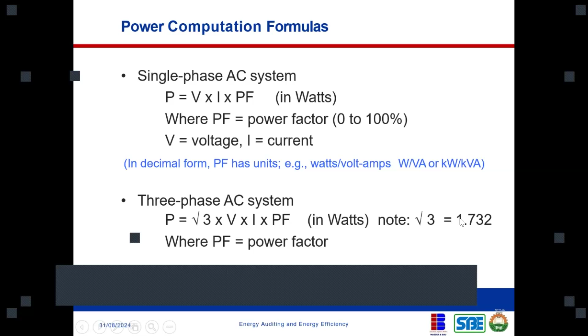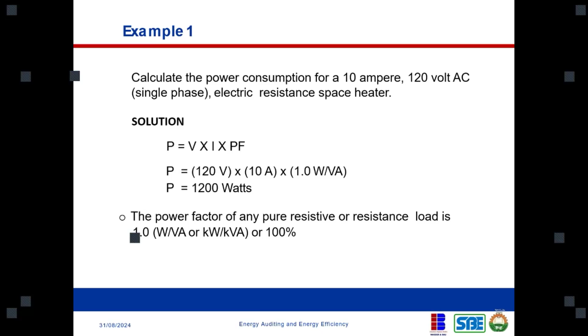So this is an example, a straightforward one. The formula is straightforward, you just need to extract your values and input them into the formula, then run a simple calculation. This asks: calculate the power consumption of a 10 ampere, 120 volt AC single phase electric resistance space heater. You'll be given your current, your voltage, and your power factor. For a resistive load, the power factor is just 100 or 1. So it's a straightforward calculation.